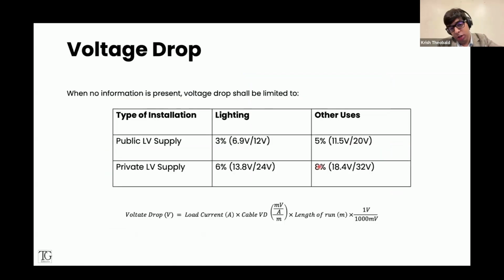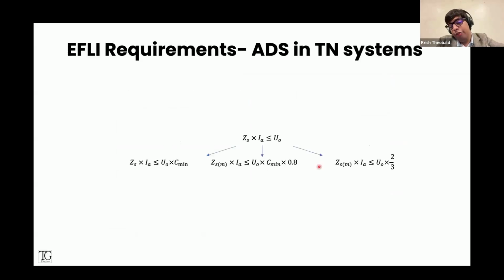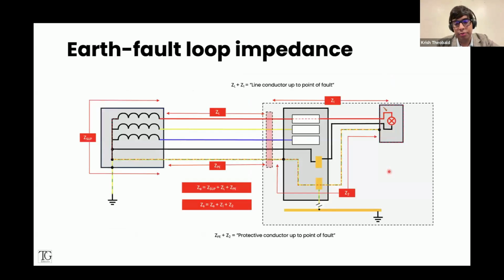Voltage drop, of course, we've got 3% and 5% for public supplies, 6% and 8% for private supplies. Earth fault loop impedance, very important again. So, the earth fault loop impedance has to be less than or equal to Uo by Ia, or Zs into Ia less than or equal to Uo. In India, we apply a two-third factor to correct for temperature. So that's that as well.